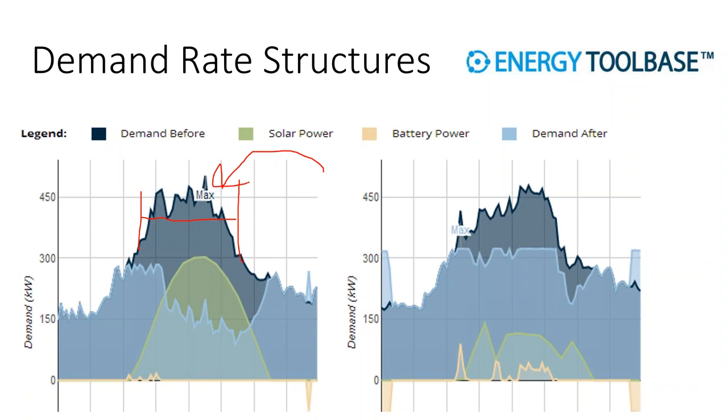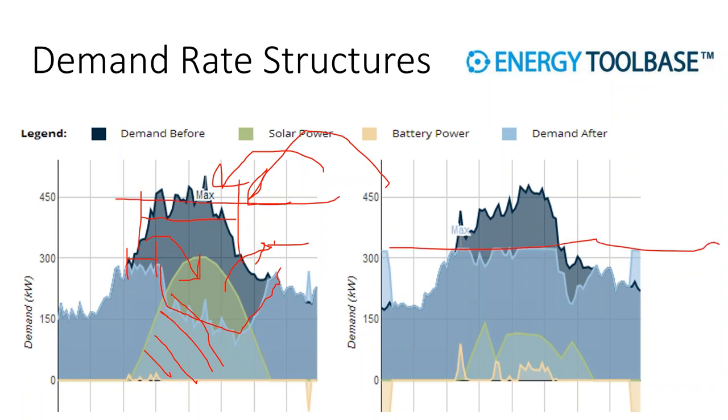But what's happening right now in the industry is there's a synergy between solar and batteries, where we have this peak demand energy being generated, and it's physically reducing the building's demand that would otherwise be up at its peak. And then when you add a battery to it, the battery doesn't need to run all day, but it can run in the morning, get recharged by solar in the afternoon, and provide additional load leveling in the evening. And furthermore, the battery doesn't need to run every single day. It only needs to run on those few days of maximum load, provided that you're just trying to give your power use a haircut, rather than try and buzz cut it.